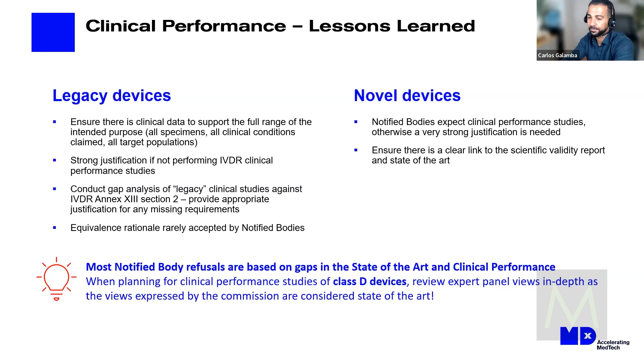So for instance, one of the issues we've got at the moment, and we're doing a lot of studies with HIV devices as well, is that finding HIV2 samples in Europe at the moment is almost impossible. And the common specifications require you to get HIV2 samples as you're trying to demonstrate your clinical performance. And it's very difficult to find them. So sometimes you'll need to think a little bit outside of the box. I've seen justifications working for using spiked samples, but typically that is accompanied by a very strong post-market performance follow-up once the device is on the market, with a clear study: this is how we're going to monitor that these spiked samples do not impact performance of our assay. We aim over the next 2 years to test these many samples and provide that evidence to the notified body. But I think it's possible to build a convincing argument. Okay, thank you. No worries.